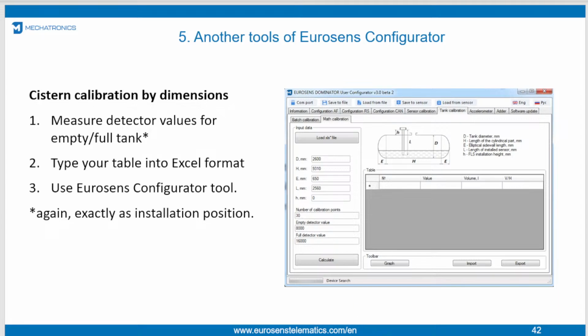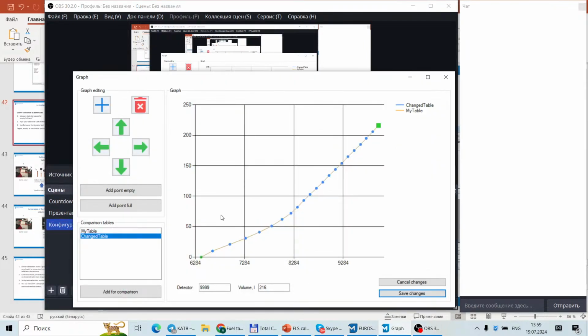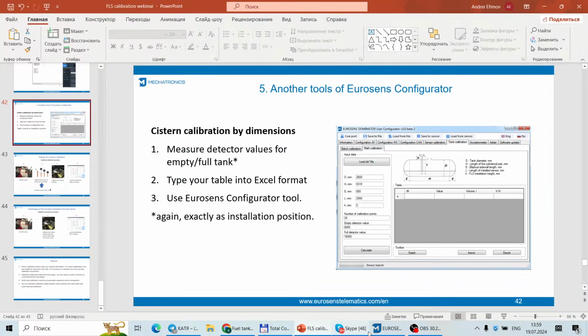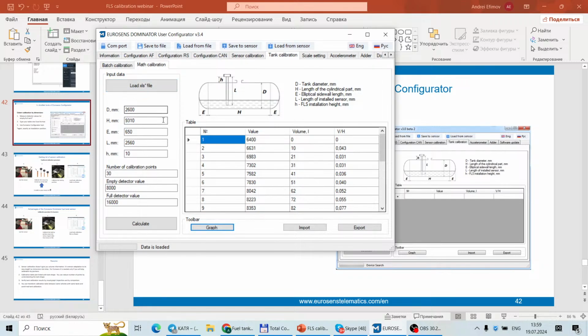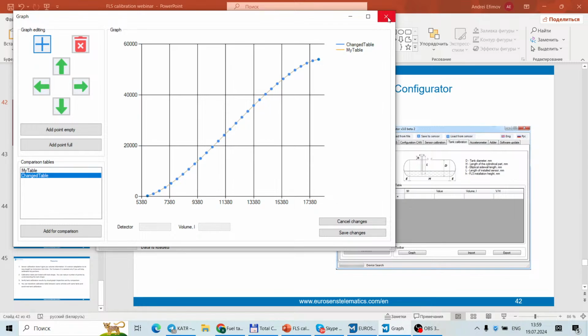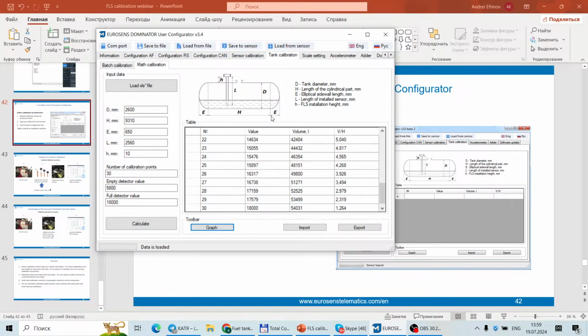How it looks in the configurator. So we are entering our dimensions according to this picture, including this height above the tank surface, and just put in our detector values from calibration and click calculate. So our calibration is ready, and we can save it into the sensor. You can see if you enter dimension E equal to 0, you will get the calibration for a horizontal cylinder without these side parts. So you can use this master also for horizontal cylinder calibration as well.